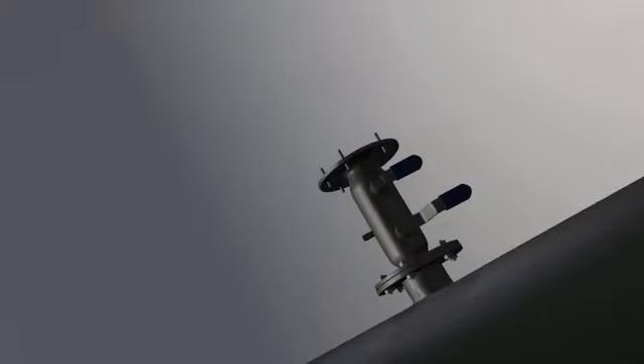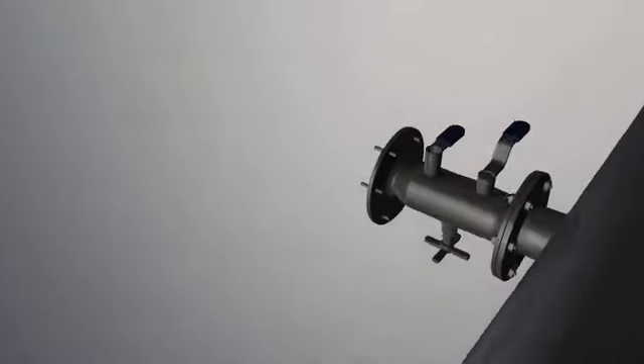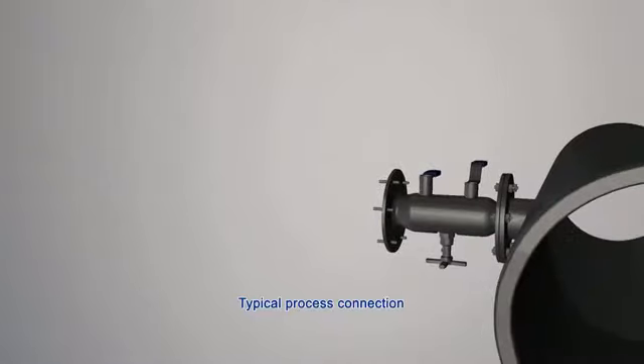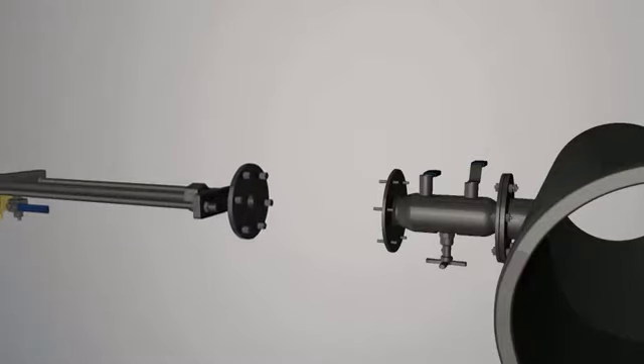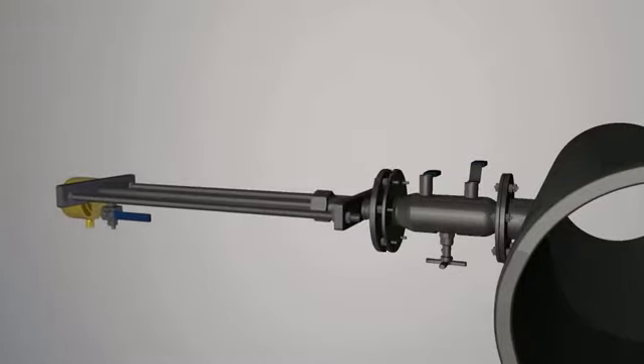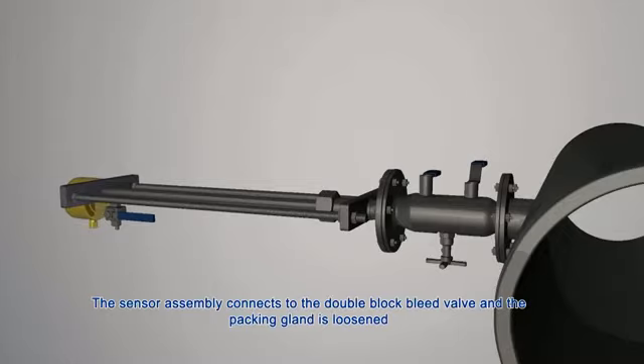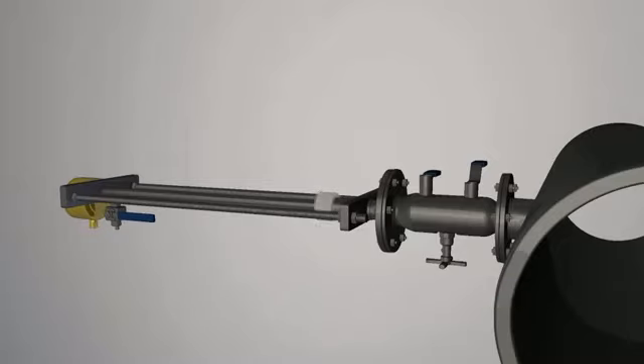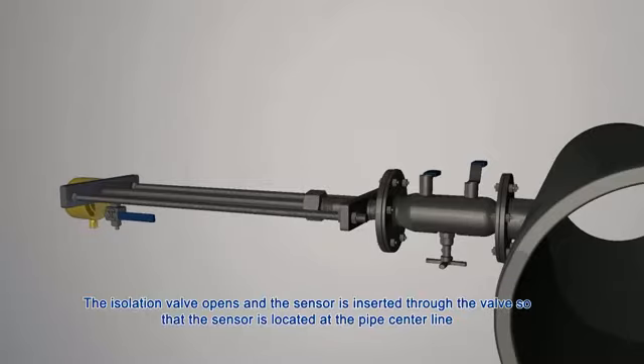A typical process connection consists of a ball valve attached to the process pipe. Shown here is an ideal installation using a double block bleed valve. The sensor assembly connects to the double block bleed valve and the packing gland is loosened. The isolation valve opens and the sensor is inserted through the valve so that the sensor is located at the pipe center line.